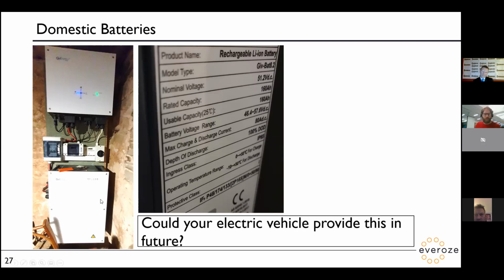As you may recall from old school electronics, your power is your voltage times your current. Its nominal voltage is 51 volts. So if you multiply 51 by 160, you get about 8 kilowatt hours. So this is a roughly 8 kilowatt hour system. I probably should have known that, but I trust the owner knows it.